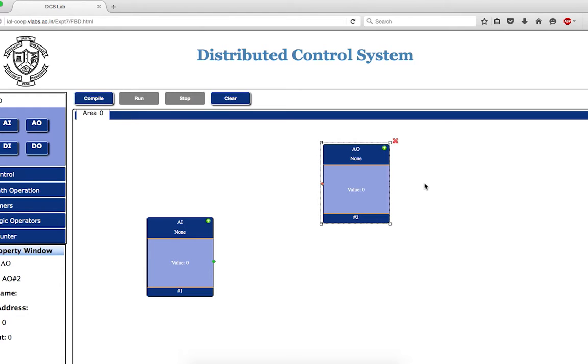But while processing all those inputs and outputs, to make the distributed control system generic in nature, irrespective of the range of the transmitter, the calculation should remain the same. That's the reason these blocks are always in the normalized form. The meaning of the word normalized is that the whole range of 4 to 20 milliampere will be converted into 0 to 100%, which becomes easy for processing.